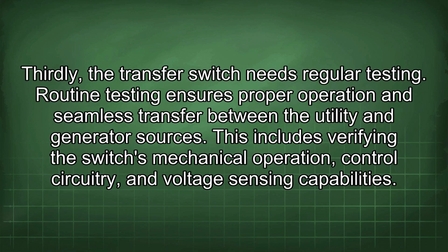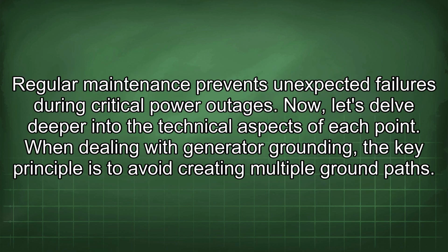Thirdly, the transfer switch needs regular testing. Routine testing ensures proper operation and seamless transfer between the utility and generator sources. This includes verifying the switch's mechanical operation, control circuitry, and voltage sensing capabilities. Regular maintenance prevents unexpected failures during critical power outages.